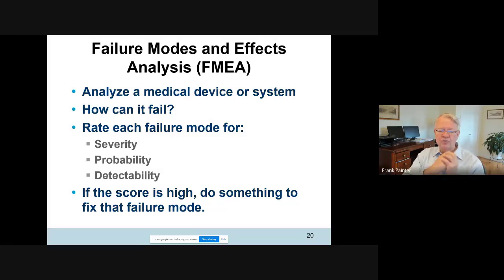The way we do this is, first of all, we look at a system or a medical device, and we say, how can it fail? Let me list all the ways of failure. And then we rate each mode of failure for severity, probability, and detectability. And we grade each failure mode. And then if the score is high, we might do something to fix that failure mode. Like, for instance, defibrillators sitting in the nurse's station that may be used to resuscitate patients who have a cardiac arrest. How can they fail?